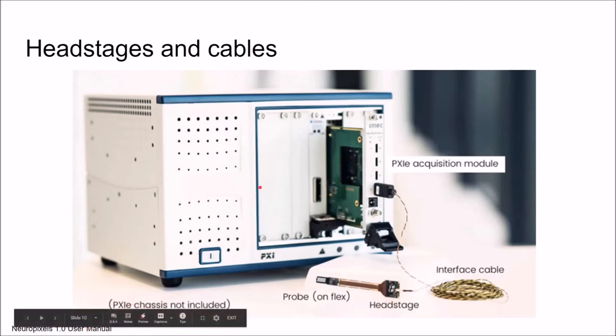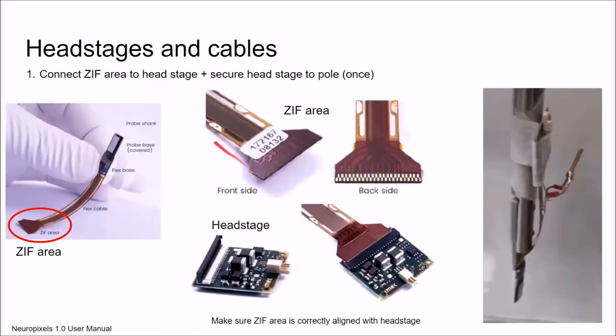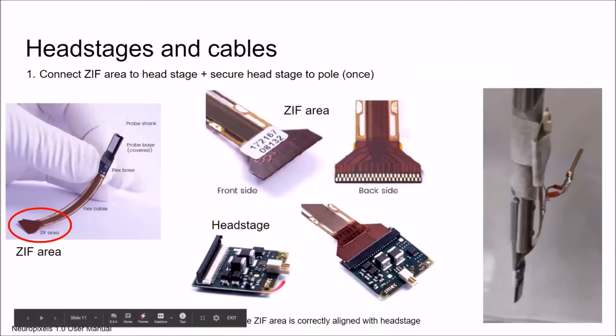Now we can connect everything. We have talked about the probe, which needs to be connected to the headstage, which needs to be connected to this interface cable, which then goes to the acquisition module, which sits in this chassis. The first step is you want to connect this ZIF area, which you can see here, to the headstage. Here is a zoom into this ZIF area. It has a front side and a back side. You need to be sure which is which. This is the headstage and you want to slide the ZIF area in the right direction into this headstage. This black part needs to be open. You slide in the ZIF area like so and then you can close the black part so it's fixed.